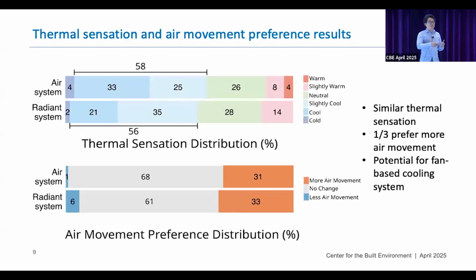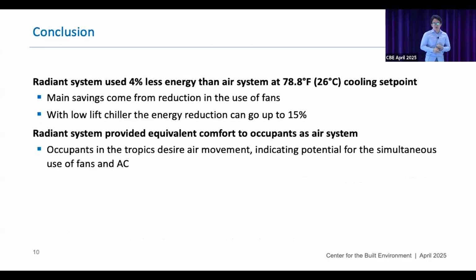And for both of the results, one third of the occupants actually prefer more air movement. So this is a potential for occupants in tropical climates that like more air movement. With more air movement, you can probably increase the set point higher and save more energy.